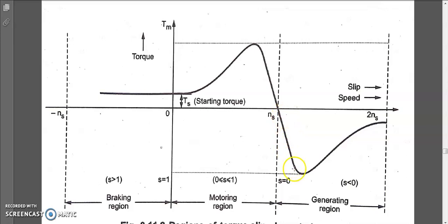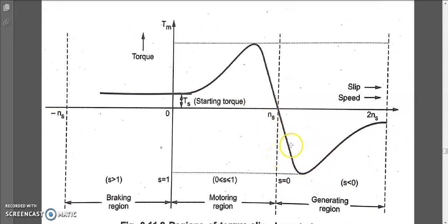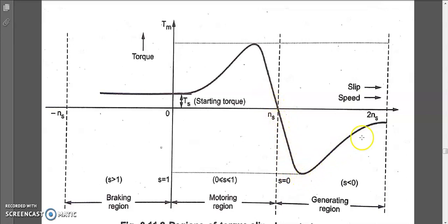Now the generating region: when the motor acts as an induction generator, we get negative slip. Until now slip has been positive because ns is always greater than n. But in the generating region, n is greater than ns, so ns minus n gives a negative slip. The generating region appears as an inverted image of the motoring region. This is only possible when the rotor rotates faster than synchronous speed.